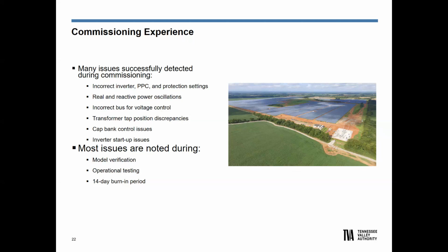Most issues we've noted are related to model verification, again, EMT model verification, and operational testing, where the person installing the actual equipment doesn't know how to do the operational testing. Because of that, we've required a 14-day burn-in period, where it's a requirement that they must have a successful 14 days' worth of run without seeing any issues from an oscillation point of view, from incorrect voltage control, all those different things. And if they do, it resets the clock once they make the change.